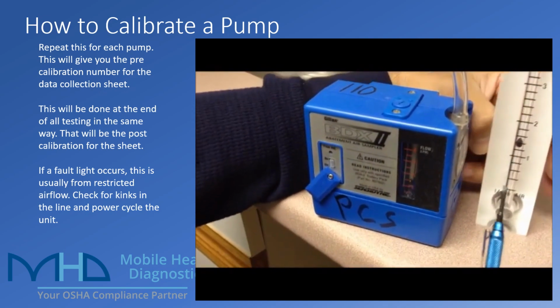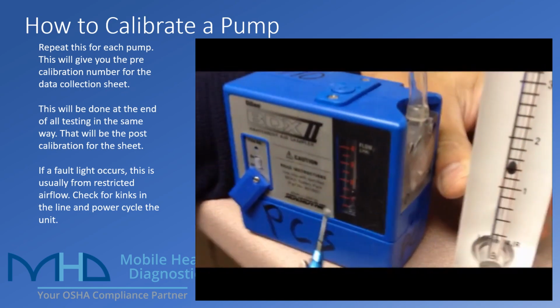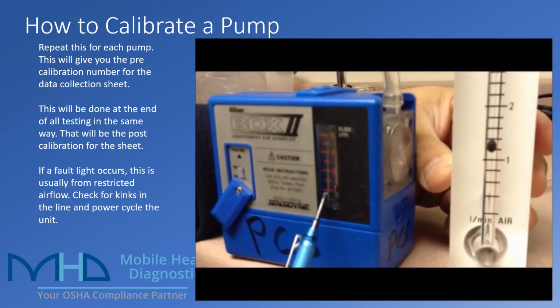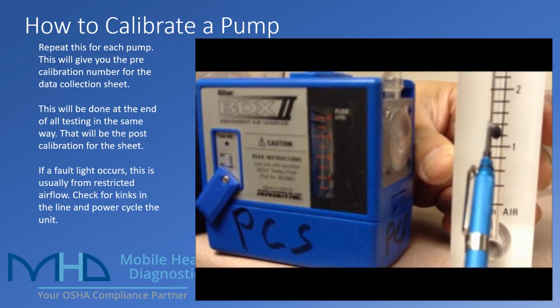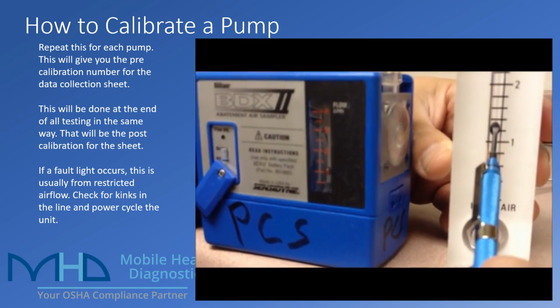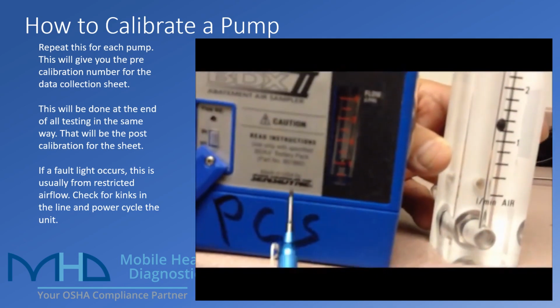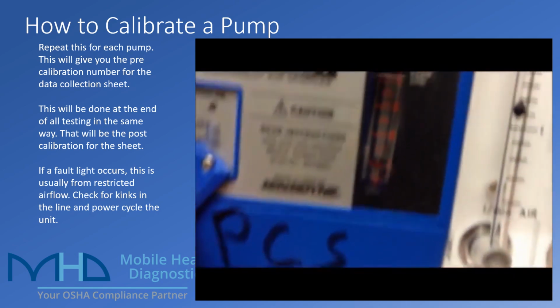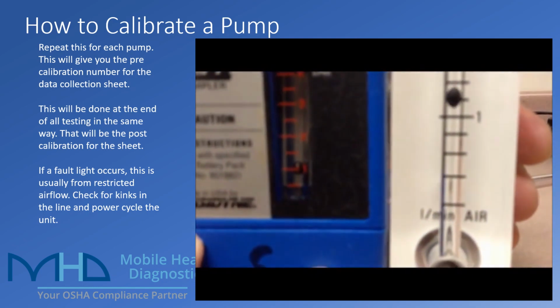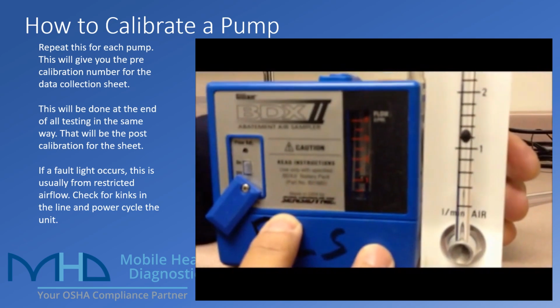So we have the main power switch on the left side there. Just above that is a small access port with a screw. There should be a small screwdriver that is provided by SGS Galson. Those are complimentary, you can keep them. And then you can use that to adjust your flow rate. So what he's going to do is reinsert the screwdriver and then just turn the pump back up. And we're going to get to the desired end state, which I believe is going to be 2 liters.